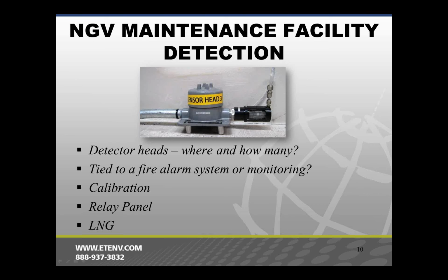You could also have it disable all non-essential electrical systems. We've seen that approach taken by some owners as well, and that's sort of on the conservative side, but possible. One thing with the gas detectors, you have generally the same requirements if you have LNG vehicles in your shop, although if you have LNG vehicles, you also need a gas detector in any service or lube pits as well, which of course are the most expensive ones to put in because you have to trench across your concrete floor.